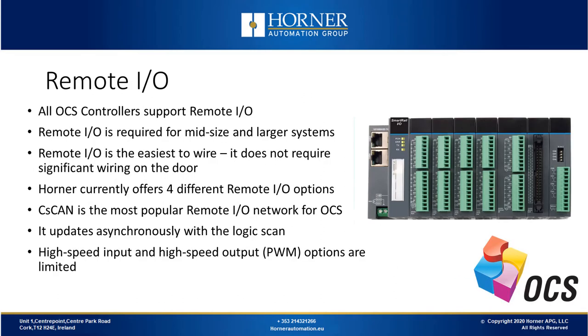Now let's talk about remote IO. All OCS controllers support remote IO. If you've got a larger application where the built-in IO is not sufficient, then you need to add it. In many ways it's easier to wire because it's mounted on the back plate with an interposing terminal strip — it doesn't require significant wiring on the door. A CAN cable or Ethernet cable is all you should need. Horner offers four different remote IO options. CsCAN is our most popular remote IO network. It's robust, it's plug and play, and it's inexpensive. It updates asynchronously with the logic scan, however there are fewer high-speed input and output options for remote IO systems.